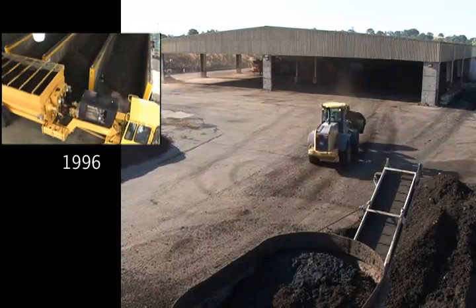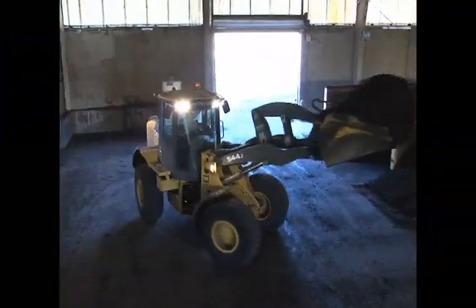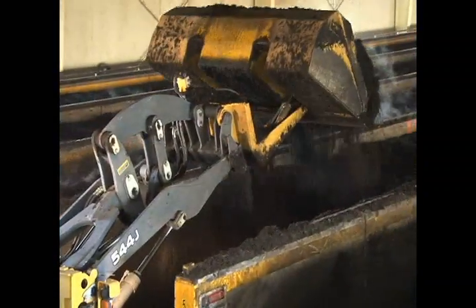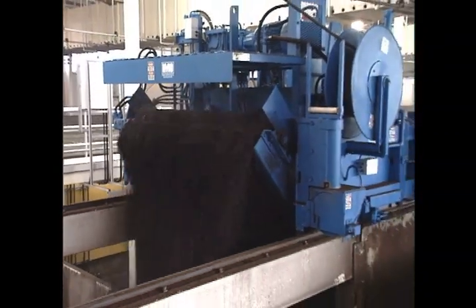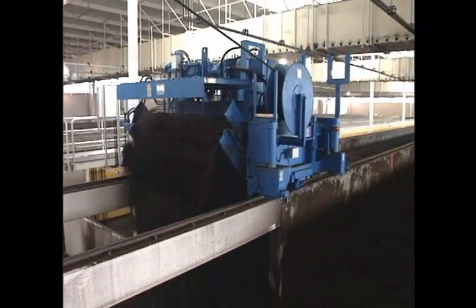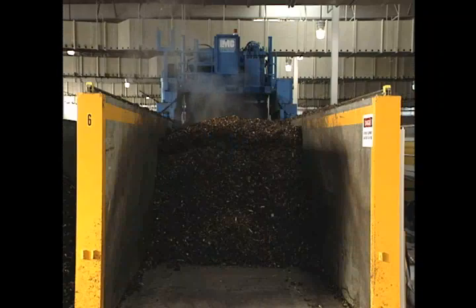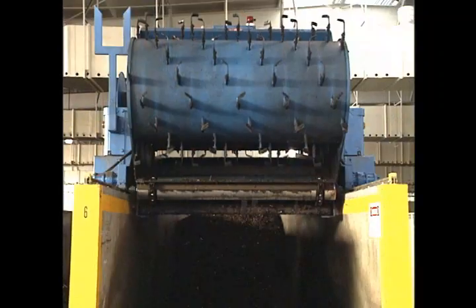Originally, the material was unloaded from the mixing truck to the front of a compost bin inside the facility. A stationary mixer used with a loader now optimizes the process. The pile is turned each day by an agitator. Starting at the rear of the bin, each pile is aerated, moved back 14 feet, and restacked behind the machine. When agitation is complete, the machine returns and moves on cross rails to the next bin. Two agitators can process the entire facility in an eight-hour day.